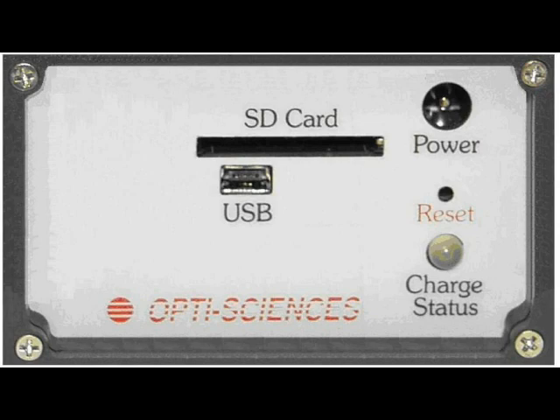Cards are available up to 2GB. The instrument also provides a USB port for direct transfer of measuring files and stored images. The fluorometer becomes a hard drive for your computer, and files can be opened in Excel or any comma-delineated software program. This technology also allows software upgrades and enhancements in the field by connecting the instrument to your computer and clicking on an OptiSciences-provided link.